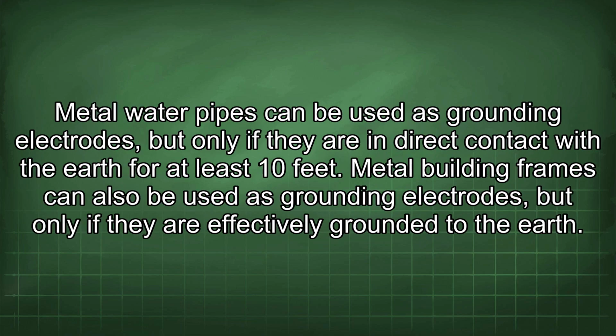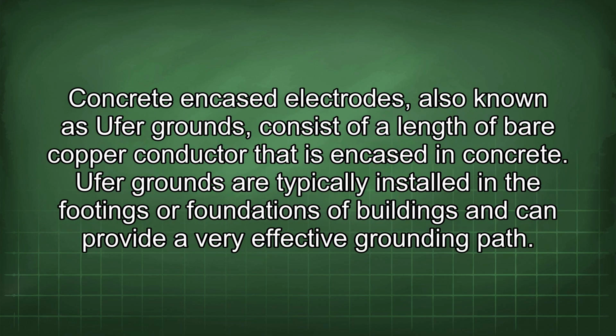Metal water pipes can be used as grounding electrodes, but only if they are in direct contact with the earth for at least 10 feet. Metal building frames can also be used as grounding electrodes, but only if they are effectively grounded to the earth. Concrete encased electrodes, also known as Ufer grounds, consist of a length of bare copper conductor that is encased in concrete. Ufer grounds are typically installed in the footings or foundations of buildings and can provide a very effective grounding path.